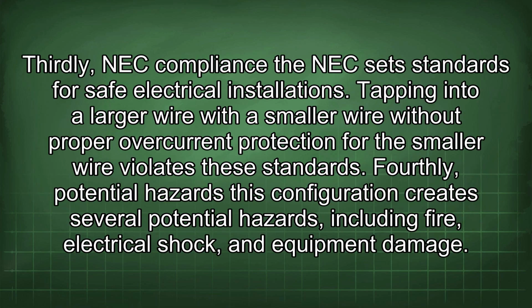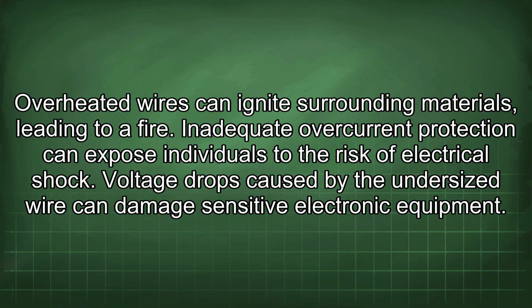The NEC sets standards for safe electrical installations. Tapping into a larger wire with a smaller wire without proper overcurrent protection for the smaller wire violates these standards. Fourthly, potential hazards. This configuration creates several potential hazards, including fire, electrical shock, and equipment damage. Overheated wires can ignite surrounding materials, leading to a fire. Inadequate overcurrent protection can expose individuals to the risk of electrical shock. Voltage drops caused by the undersized wire can damage sensitive electronic equipment.